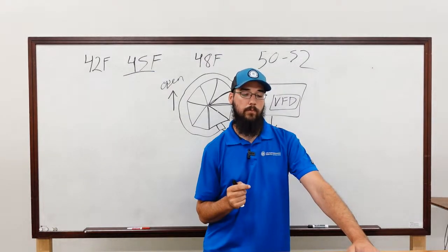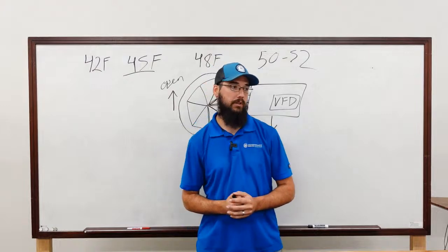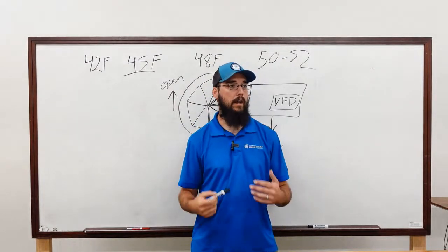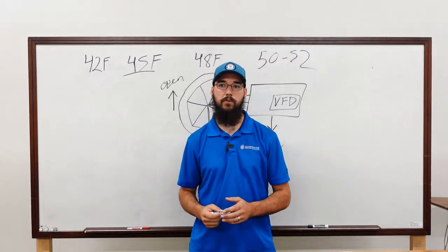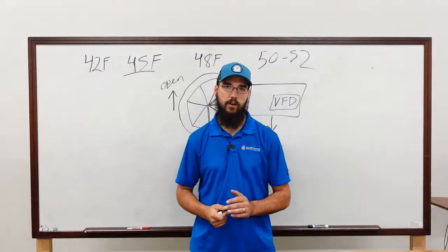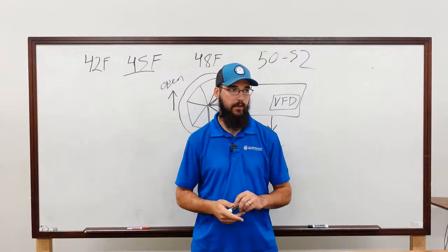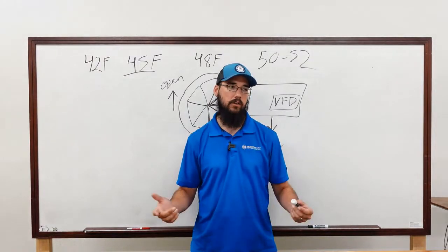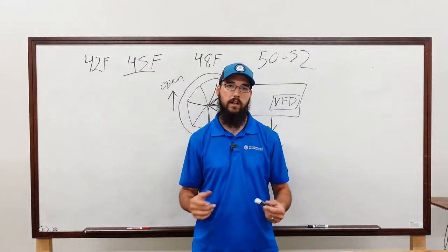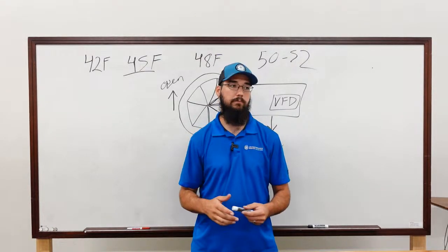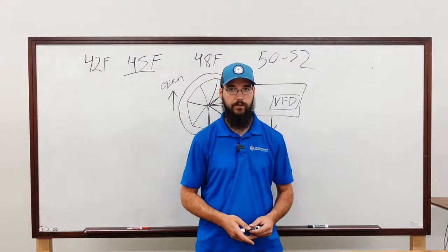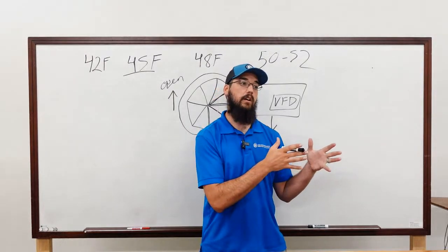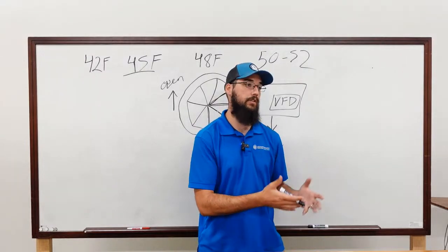So when you talk about the power feed to a building, most of them in our area are a Y transformer. I don't think we service any building currently that has a delta feed into it. And you would know you have a delta feed because you have what they call a wild leg. You have one leg, you read it to ground, and it's going to be some weird, wacky voltage, right? It's going to be off. And that can kind of vary, and that is a symptom of a delta transformer.